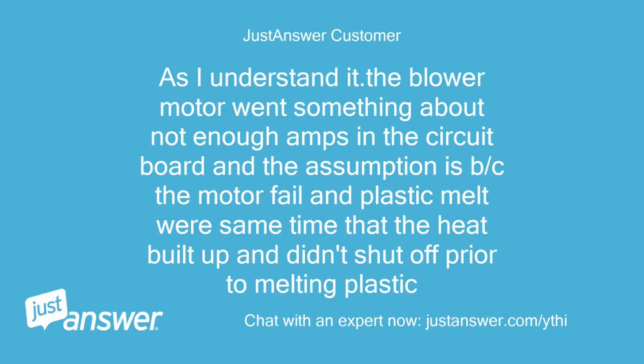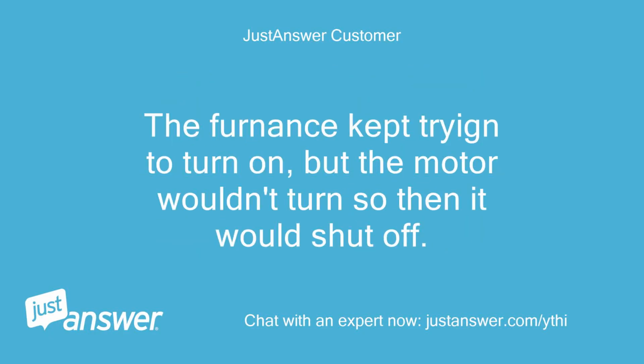As I understand it, the blower motor went, something about not enough amps in the circuit board, and the assumption is the motor failure and plastic melt happened at the same time, so the heat built up and didn't shut off prior to melting the plastic. The furnace kept trying to turn on, but the motor wouldn't turn, so then it would shut off.